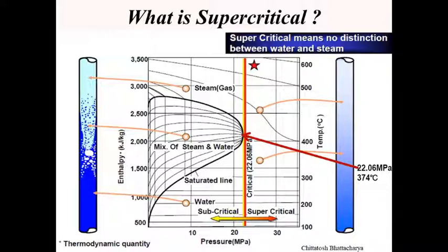Whenever we increase the boiler operating pressure from subcritical regime to supercritical, that means above 224.6 kg per centimeter square, naturally the requirement of latent heat addition is totally removed. So we get, just after sensible heat addition, water flashes into steam, and due to this type of situation, there is no two phase condition heat addition.